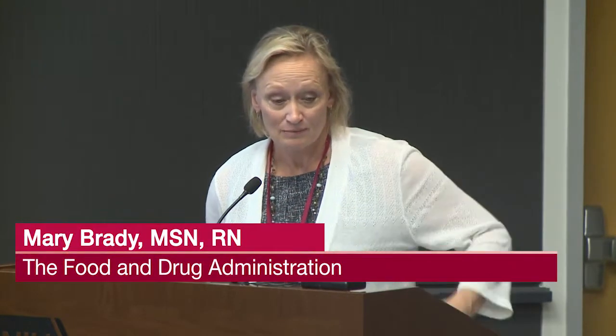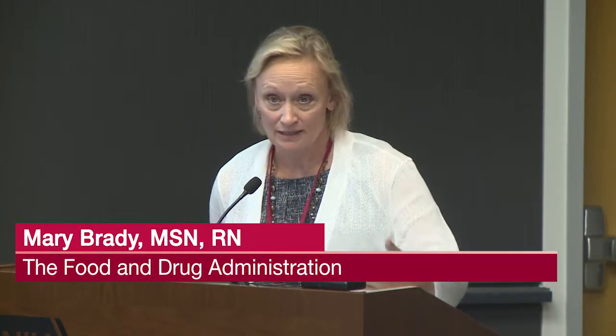And I know something I missed here were alarms. When you're in a home environment, if you have somebody on ventilator therapy laying in bed, you're going to be going out to do the dishes or the gardening—you're not going to be sitting there waiting for that alarm to go off. So we've requested that manufacturers have two different types of alarms on their home use device, whether tactile and auditory, visual and auditory, or visual and tactile, so people have two different ways of knowing an alarm is going off.